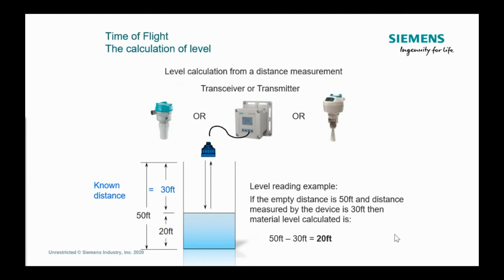When I'm doing troubleshooting, I like to put the instrument in distance mode, not level mode. And the reason for that is this. In distance mode, if my instrument says 13.5 feet, I can grab a measuring tape and measure down to my material and see, yeah, that's 13 feet 6 inches. Okay, I know that my instrument is measuring the right distance. It's pretty easy to visually check. If you're in level mode, you have to check several different things.